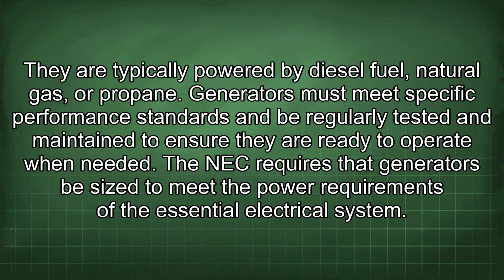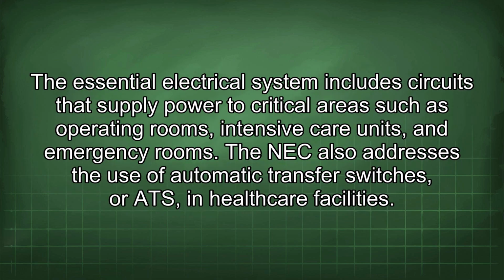Generators must meet specific performance standards and be regularly tested and maintained to ensure they are ready to operate when needed. The NEC requires that generators be sized to meet the power requirements of the essential electrical system. The essential electrical system includes circuits that supply power to critical areas such as operating rooms, intensive care units, and emergency rooms. The NEC also addresses the use of automatic transfer switches, or ATS, in healthcare facilities.